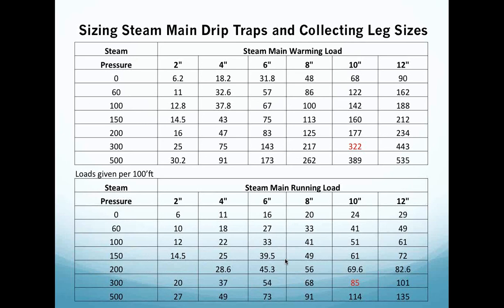If this 10-inch steam line during warm-up can produce 322 pounds per hour per 100 feet, you can generate a lot of condensate on that startup condition. Now, what I want you to know is there is a running load when the whole system is up to temperature that is different than that warming load. So in a 300-pound steam system on a 10-inch main at running load, at running temperatures, the actual condensate generation ability of that line is only 85 pounds per hour per 100 feet. So I wanted you to see the difference on a warming load versus a running load.